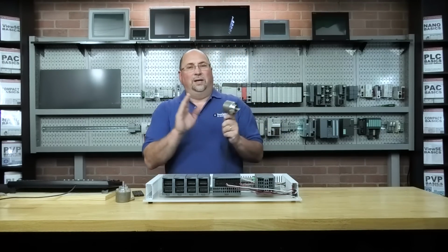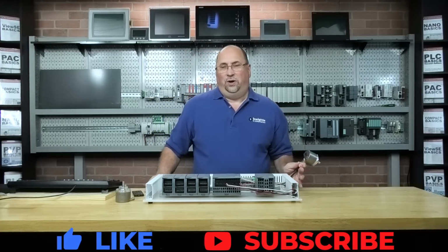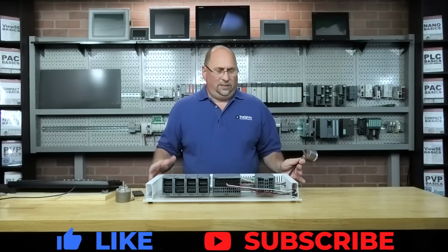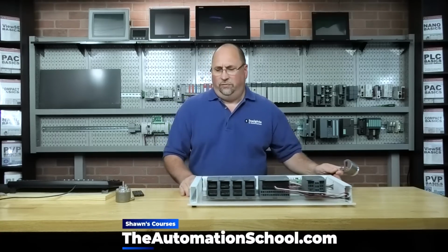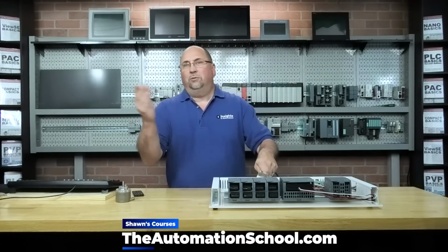with an encoder. Now, you may want to use the HSC instruction, or I think there's an advanced or extended version of it too, because you may want to reset it, or you may want to preload it. There are all these things you might want to do in your code, so that's why you might want to use that instruction. But for this video, to stay in step with the previous ones we did, we would just show the basics of connecting up the encoder to the S7-1200 and the minimum steps you need to do to get that HSC working.